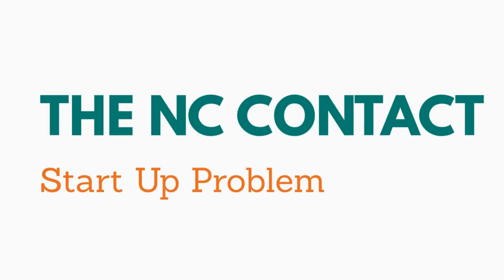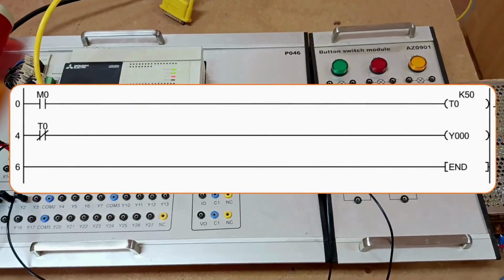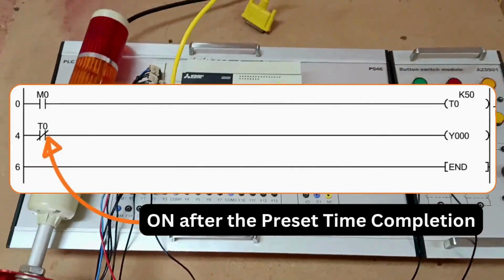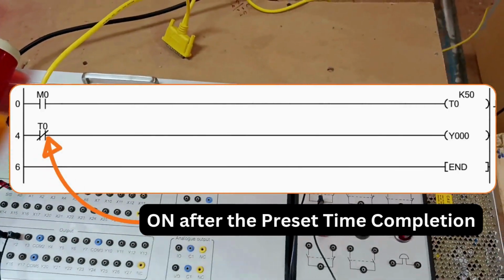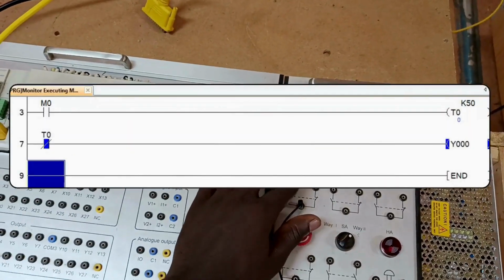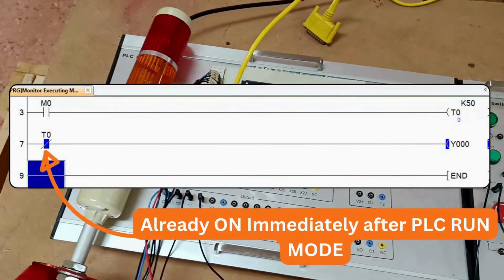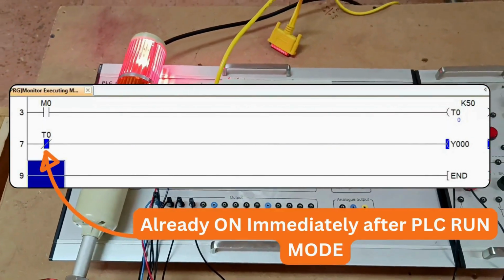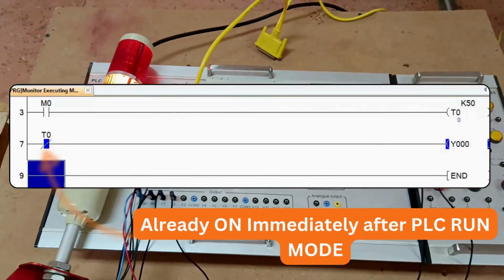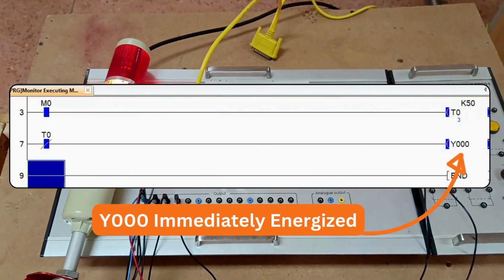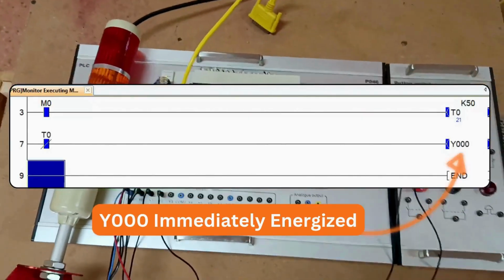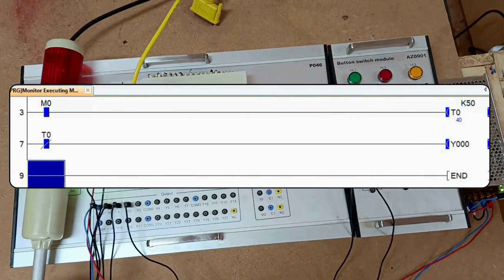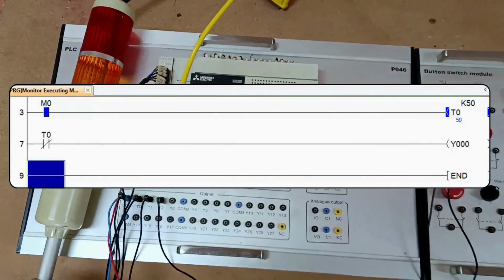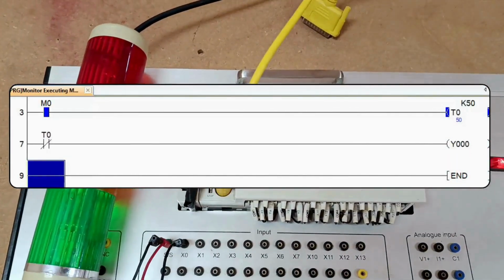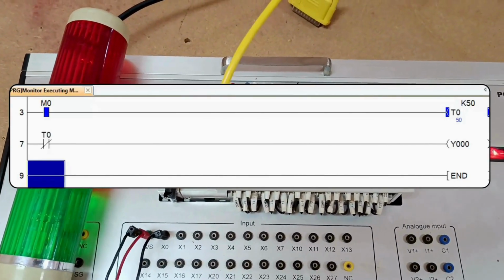But before we use these timer contacts, there's one behavior you need to understand. Look at this normally closed T0 contact. The timer hasn't been triggered yet, so T0 is not complete. That means its normally closed contact is closed. And because that contact is closed, Y0 can be energized immediately. So if you ever see an output turn on before your sequence has started, don't immediately blame the timer. Check the normal state of the timer contact you're using.